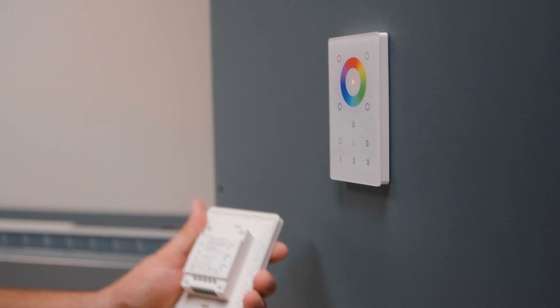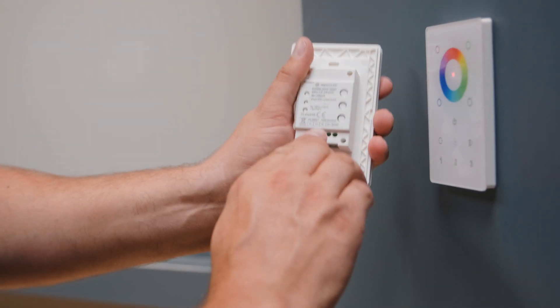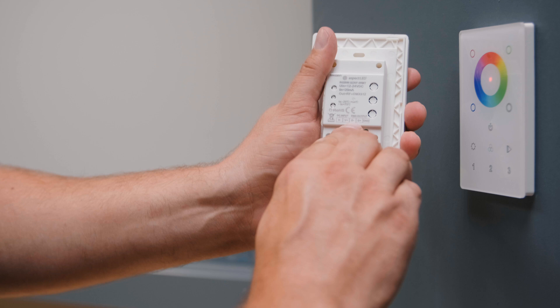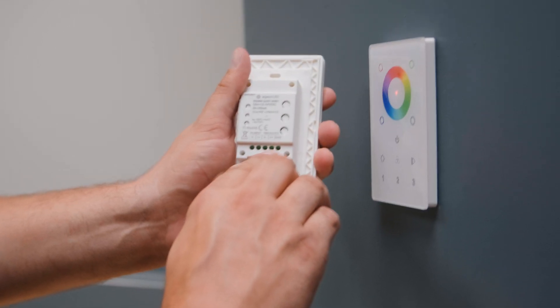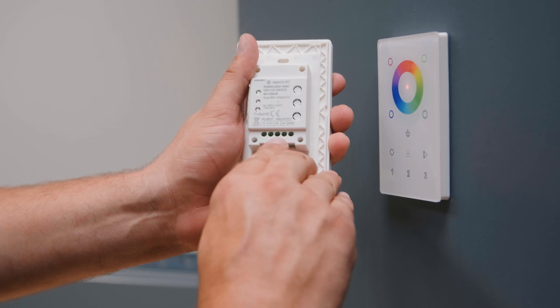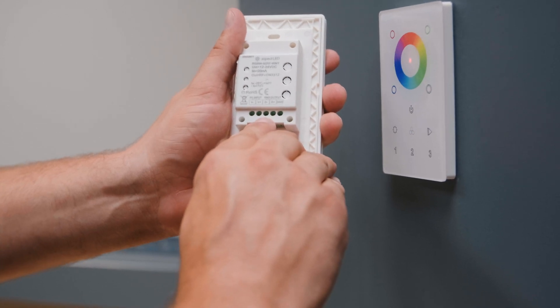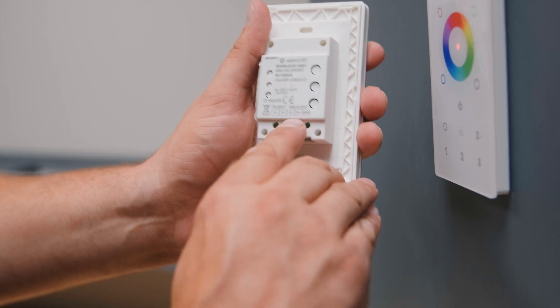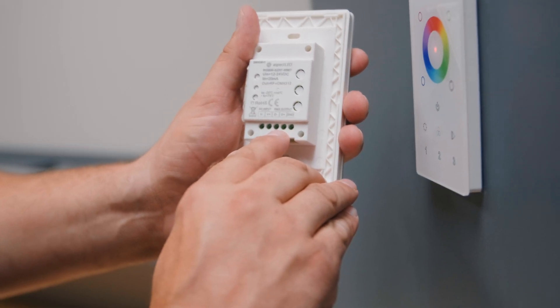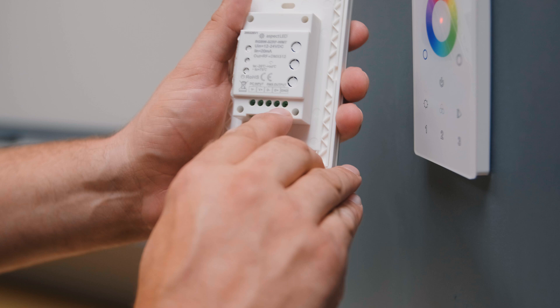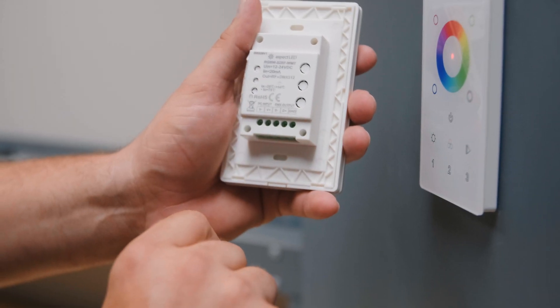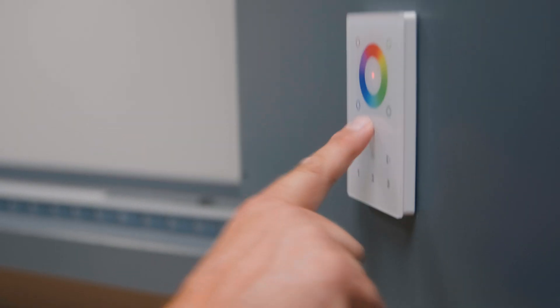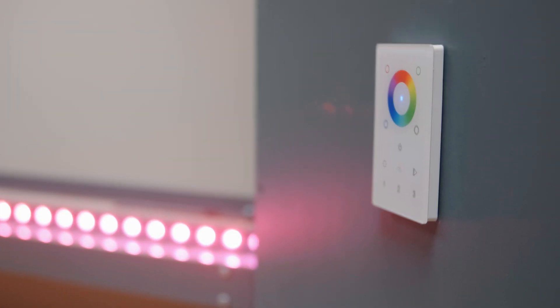On the back of this wall controller you will see there's actually DMX output for D minus, D plus and ground and we've connected on that device the D minus which was our blue wire went to this port. The D plus went to this port and the ground which was our black wire went to this port and then we have a power supply powering this and when we turn it on the device lights right up.